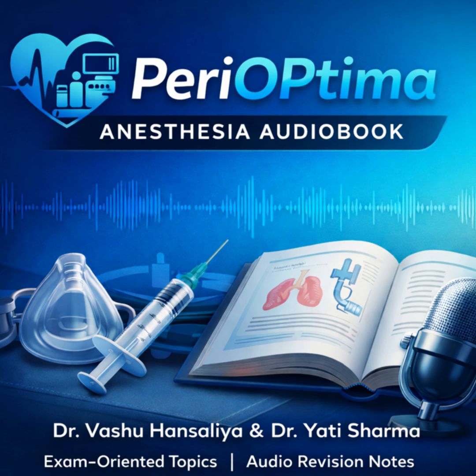Let's do it. Rapid fire. Are you ready? Ready. 1. Definition is an implantable pulse generator for bradyarrhythmias. 2. Main indications are sick sinus syndrome, complete block, and Mobitz 2. 3. NBG codes. Position 1 is paced, 2 is sensed, 3 is response. 4. VOO is asynchronous, fixed rate. Good for cautery, bad otherwise.